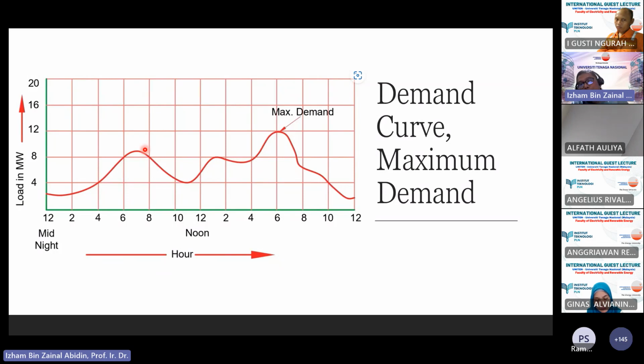So that's why in the power system network, you always monitor frequency as one of the elements, because I cannot let my frequency go too low and it cannot be too high. If I have too much generation power and not enough load, frequency will go up. If I have more load but not enough power, my frequency will go down. So having this demand curve is very important, because I need to tell the generators when to switch on, when to switch off, when to increase power, and when to reduce power, so that I can always continue to meet the demand and at the same time maintain the right frequency.